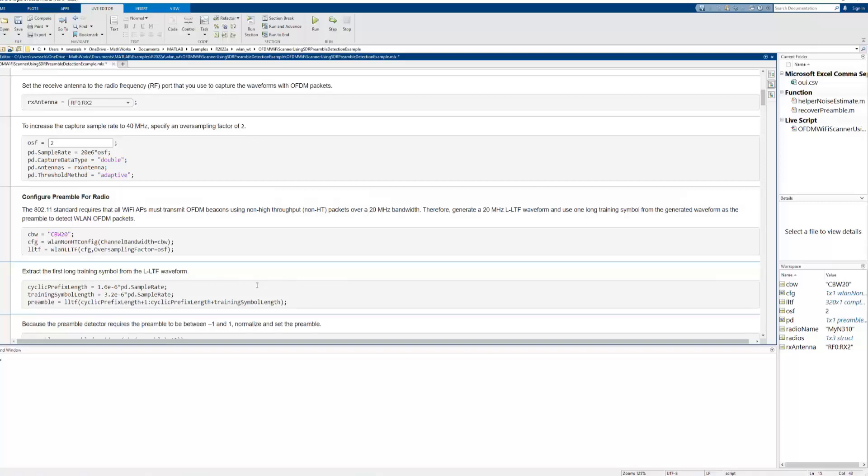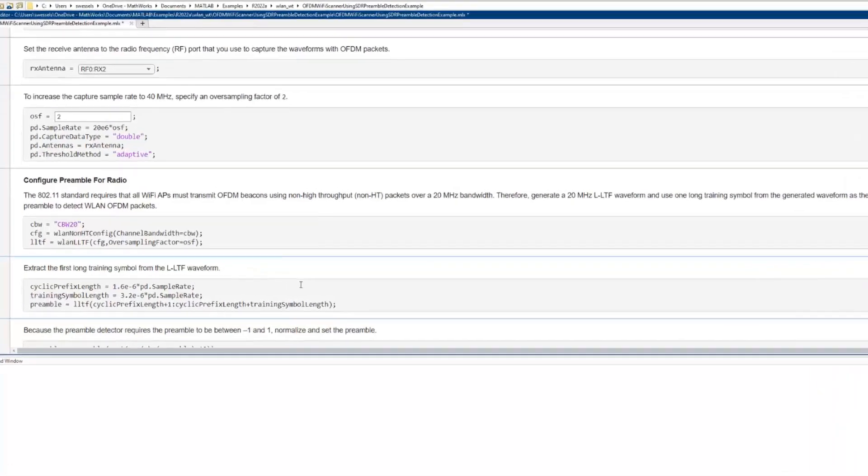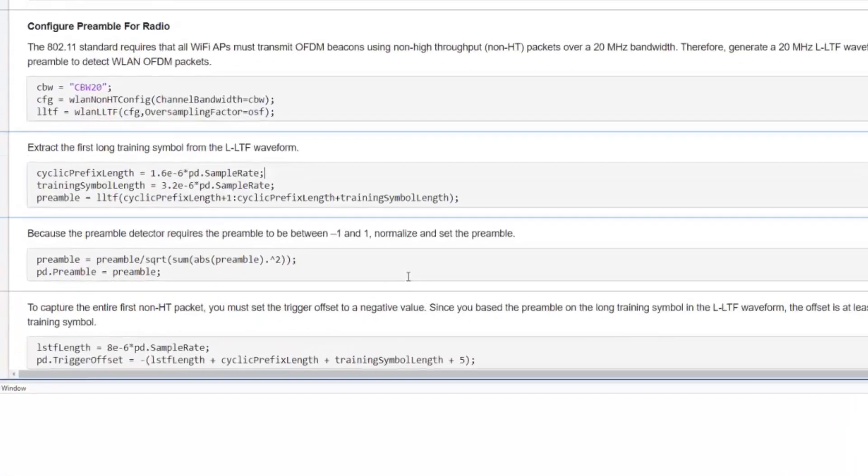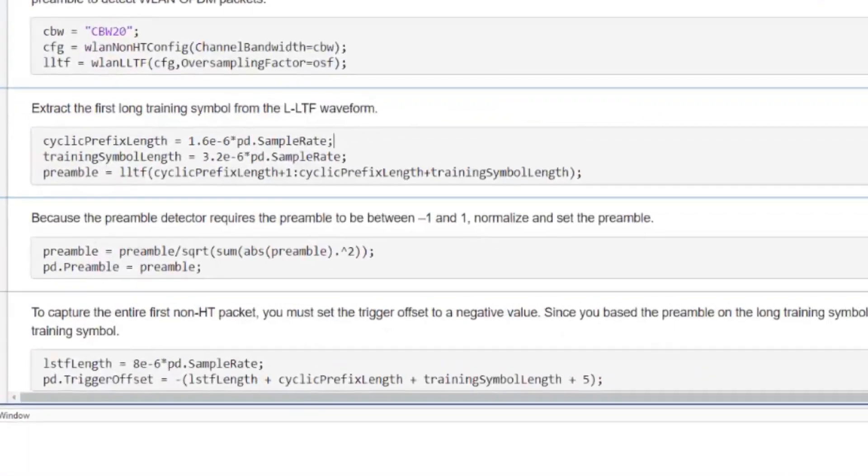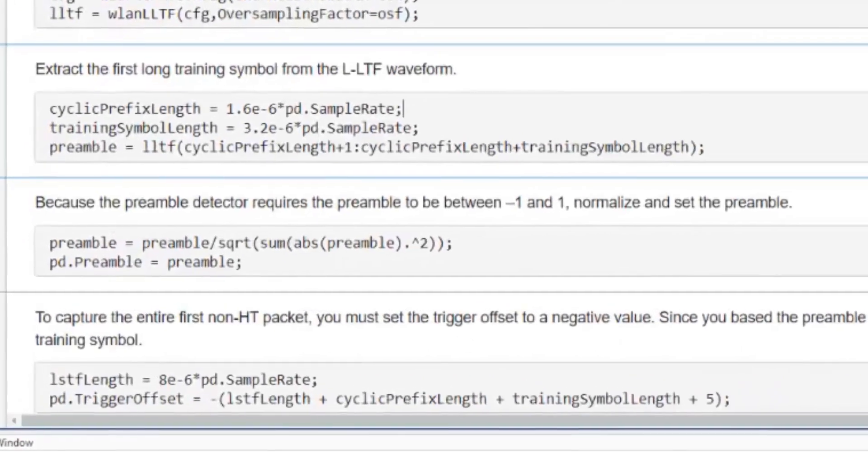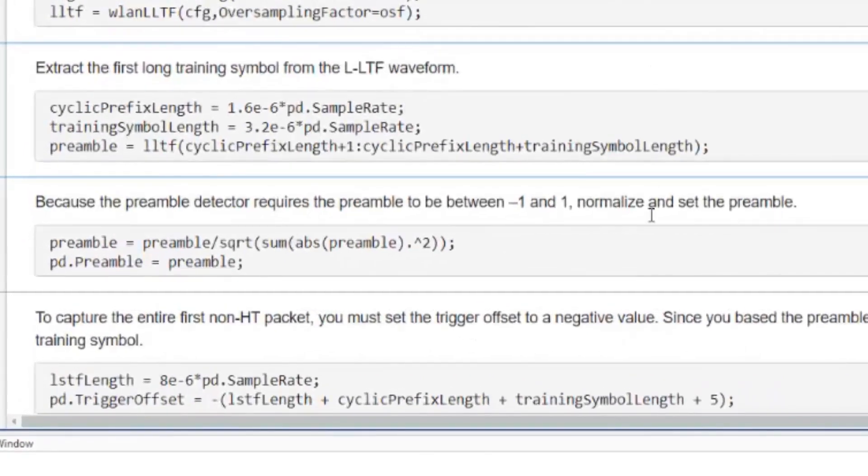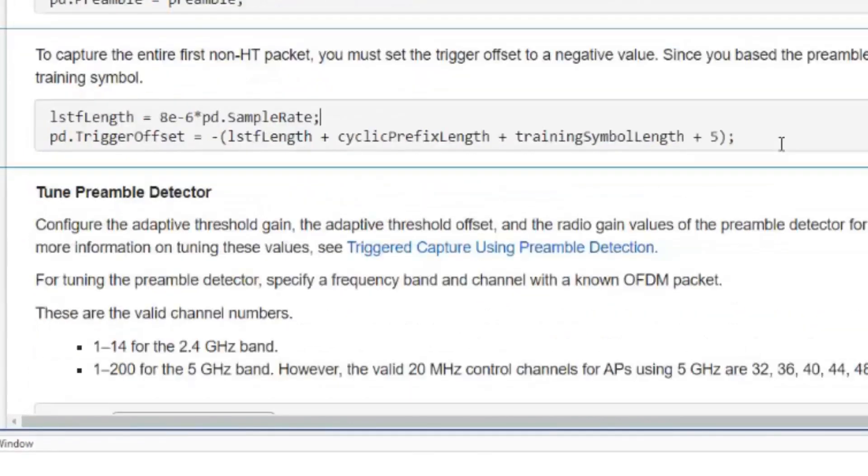Then, we set a negative trigger offset from the trigger point to capture the whole wireless LAN packet and not just from the point of detection onwards.